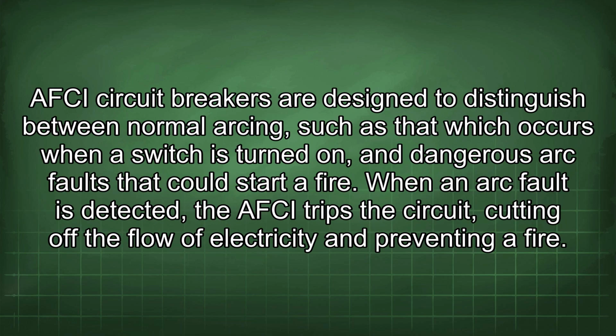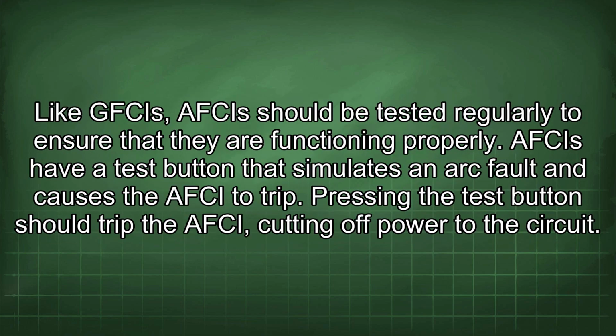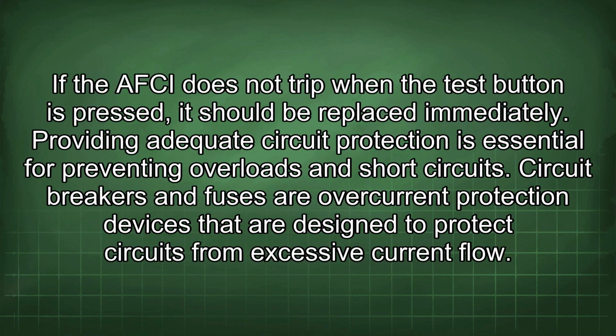AFCI circuit breakers are designed to distinguish between normal arcing, such as that which occurs when a switch is turned on, and dangerous arc faults that could start a fire. When an arc fault is detected, the AFCI trips the circuit, cutting off the flow of electricity and preventing a fire. Like GFCIs, AFCIs should be tested regularly to ensure that they are functioning properly. AFCIs have a test button that simulates an arc fault and causes the AFCI to trip. Pressing the test button should trip the AFCI, cutting off power to the circuit. If the AFCI does not trip when the test button is pressed, it should be replaced immediately.